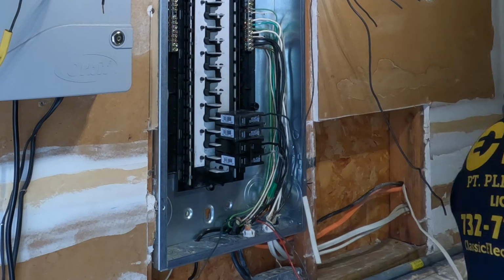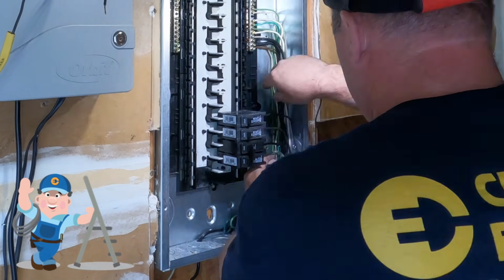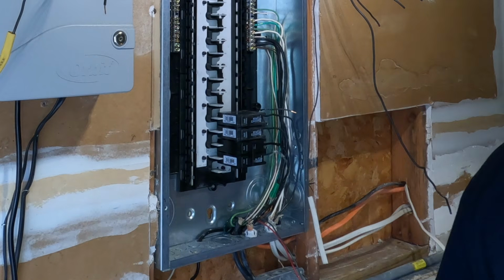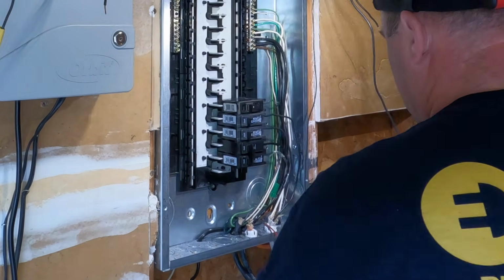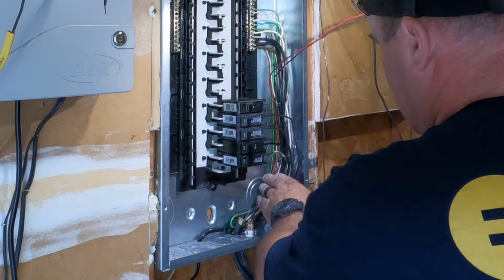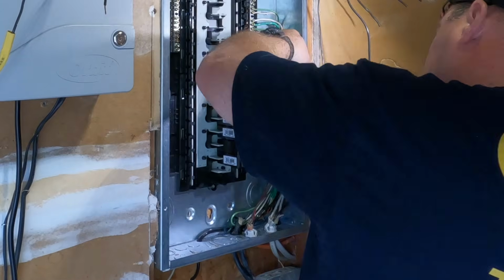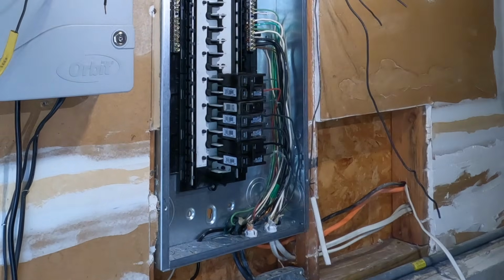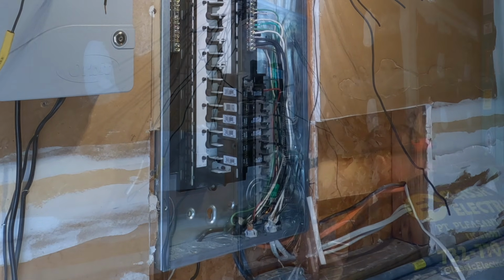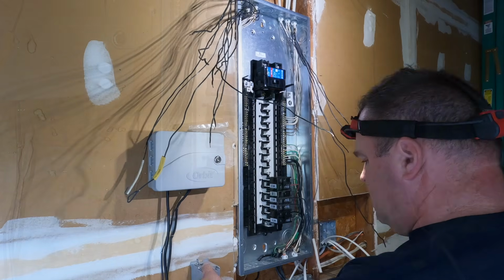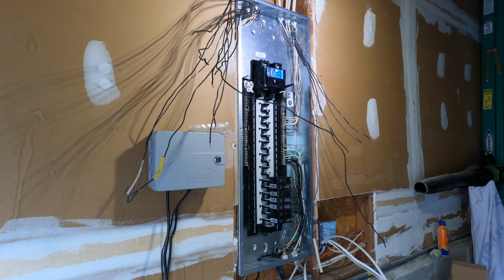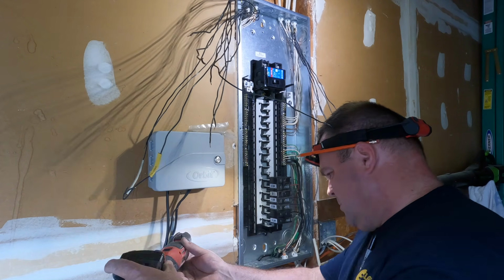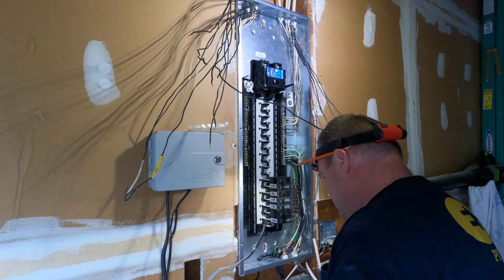I believe there was some PVC conduit that had two or three wires. I don't know what the heck it was doing, but I hooked it up the same way I found it, so it would continue working. And the orange wire is your condensing unit. And then there's a GFCI receptacle that used to be underneath the panel that I'm moving over to the right, because there wasn't enough room under the panel to redo another one.